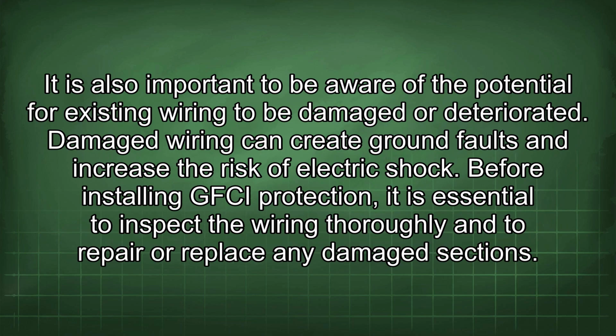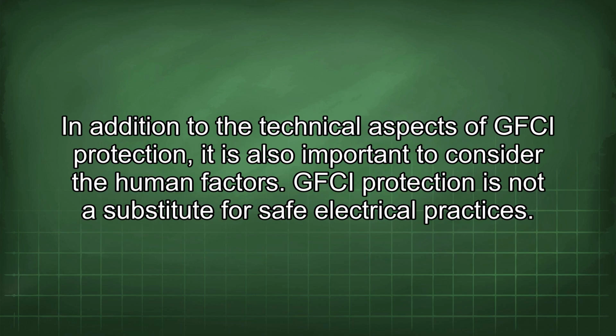It is also important to be aware of the potential for existing wiring to be damaged or deteriorated. Damaged wiring can create ground faults and increase the risk of electric shock. Before installing GFCI protection, it is essential to inspect the wiring thoroughly and to repair or replace any damaged sections. In addition to the technical aspects of GFCI protection, it is also important to consider the human factors. GFCI protection is not a substitute for safe electrical practices.